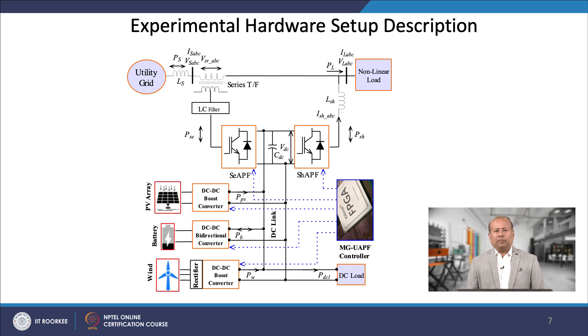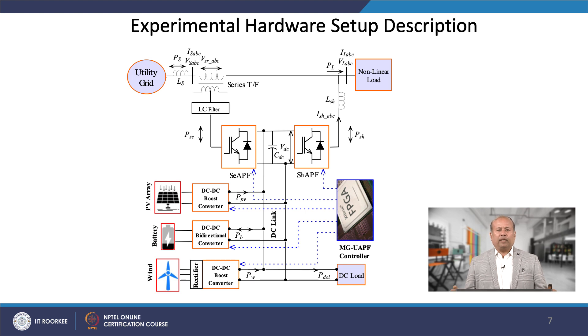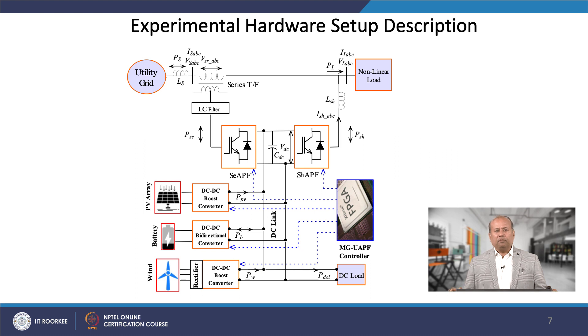At the same time, the shunt active filter behaves as a pure sinusoidal voltage source and offers a low impedance path for harmonics. Therefore, the flow of harmonic current through the grid is effectively blocked. The load fed through a diode bridge rectifier is treated as a non-linear load. For microgrid utilization, the emulated renewable energy sources are connected at the DC link with DC-DC boost converters. In addition, the battery is connected to the common DC link through a bidirectional DC-DC converter.